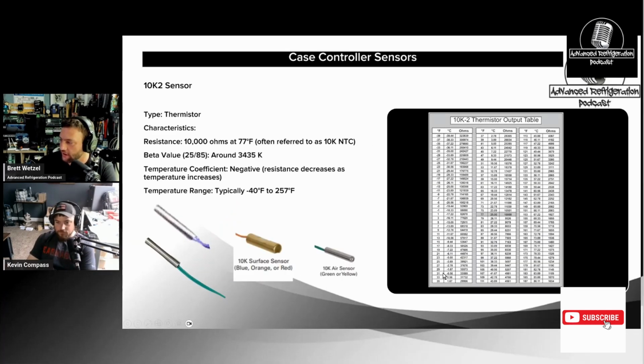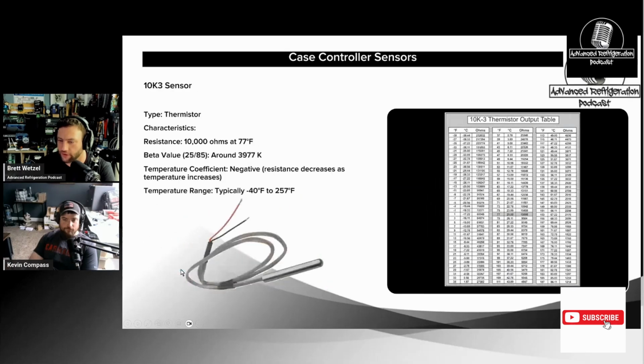So like down here at 29 degrees on the 10K2, you have 35,573. And if we go to the other one at 29, it's 31,878. So it's still 10,000 ohms at 77 degrees, but then when you start getting lower in temperature, the curve is basically different. So that's the one thing with sensors - sensors are not linear. There's not, for every 1 degree, X amount of resistance rise. They're not linear.